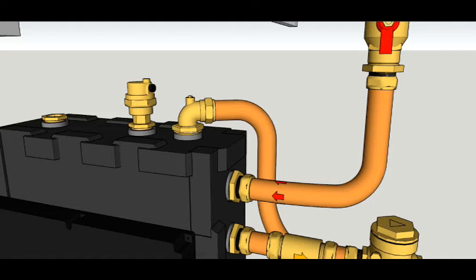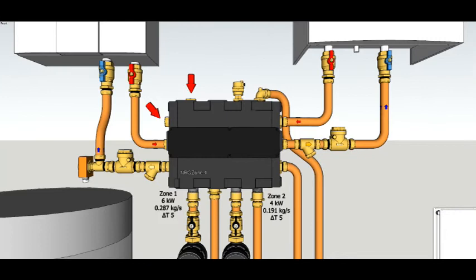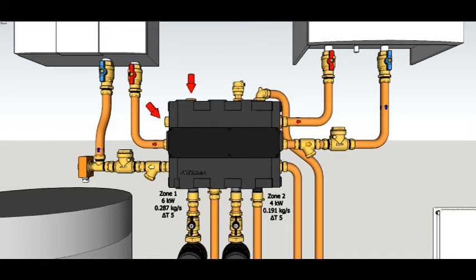You can see the two arrows at the top right hand corner - they're spare ports that could be used for instance for filling the system, or maybe you want to use the top one for adding chemicals into the system. This replaces the dosing pot but it puts the water or the chemicals directly into the path of all of the water in the zones and all of the water heading back to the boiler. It couldn't be a better location to put a dosing pot.